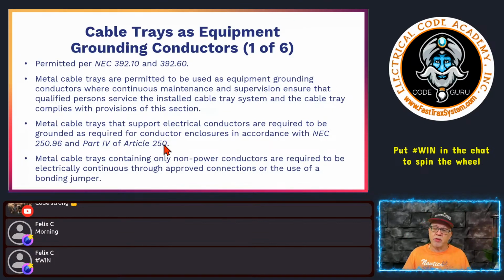And that's real important when you read rules that talk about raceways. They don't necessarily apply to cable trays, although cable trays obviously have their own rules that you have to follow, right? Okay. So here you also see that metal cable trays containing only non-power conductors, okay, are required to be electrically continuous through approved connections or the use of a bonding jumper, okay? So there you go.